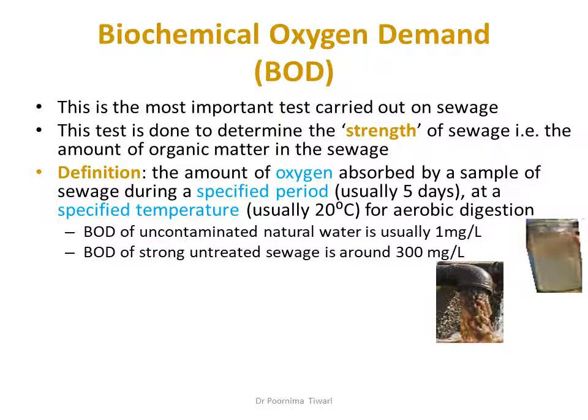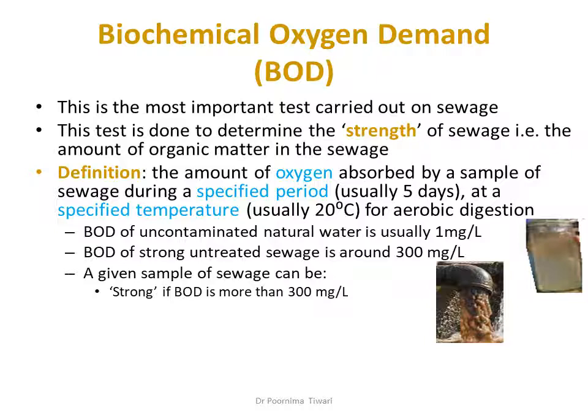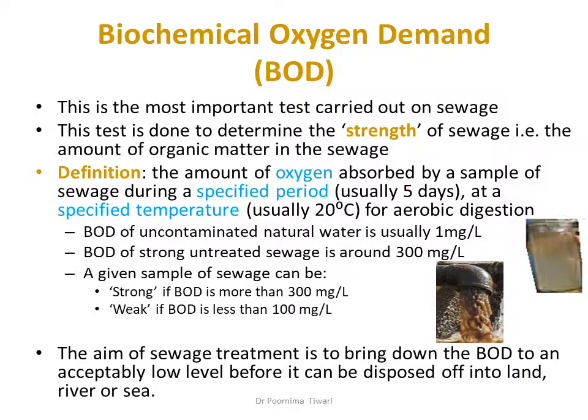Compared to BOD of strong untreated sewage which is around 300 mg per litre. A given sample of sewage is called strong if the BOD is more than 300 mg per litre, and weak if BOD is less than 100 mg per litre. The aim of sewage treatment is to bring down the BOD to an acceptably low level before it can be disposed of into land, river, or sea, whichever is feasible.